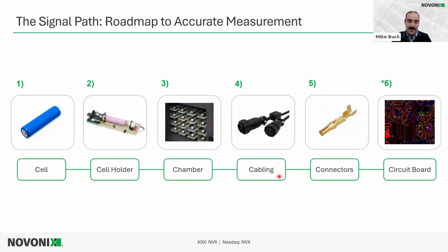The cabling, once again, should not be neglected, because it's really the bridge between the instrument and the cell holders. This cabling is what's going to block your EMI, your magnetic field interference. It's important to make sure the junctions and connections flow correctly. If there's any impedance changes between the cables, this causes measurement skew and major issues. So make sure you have correct cabling, proper twisted pair to avoid crosstalk, inductive shields, and inductor chokes—these are all important for keeping cable magnetic interference down and signals strong.